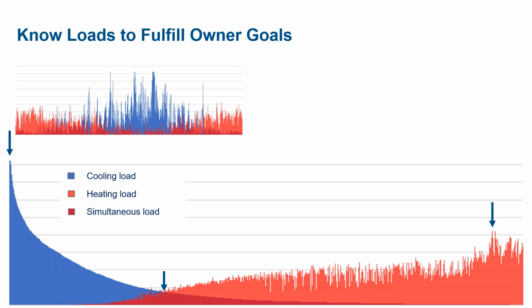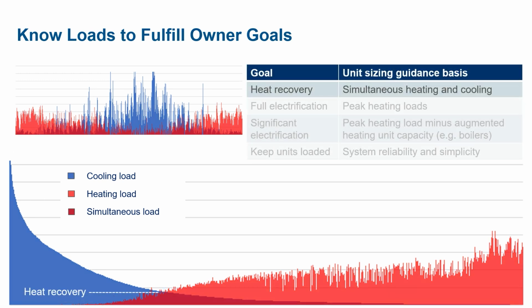When decarbonization is important, there are varying degrees to which it might be taken. If the intent is to recover heat, we want units with capacity near or below the peak simultaneous heating and cooling loads. Ideally, the equipment captures a base load, recovering heat all or most of the time. Anything beyond this leads to higher installation costs and increased operational hours with little or no load.